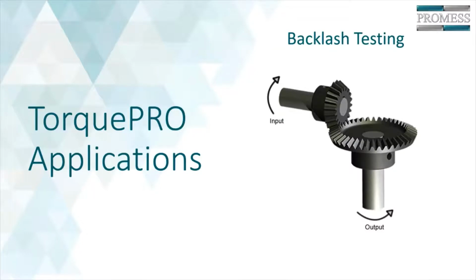Lash is one of the most common applications we see the Torque Pro used for. Lash is very important. It's performed to determine tolerance or play between two components in an assembly. The most common application for lash testing is on gear sets. Single point or static backlash testing holds one gear fixed while the other is rotated to a specific torque in both directions. The positional difference between positive and negative torque directly correlates with lash in the assembly.